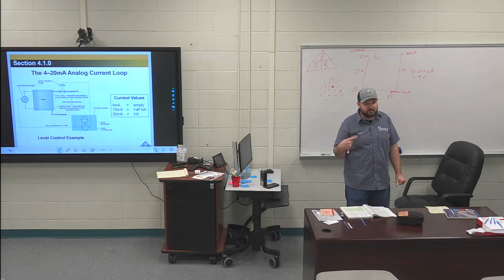A characteristic of an isolated electrical circuit is that the current will be constant at every point along the circuit. Therefore, current makes a better carrier for precision signals. So we're saying this stuff is wired in series, right? If I have stuff wired in series, I have a voltage drop across each load. That's why they don't use 1 to 5 volt signals. But my current is the same at every series load. So that's why it's easier to use a 4 to 20 milliamp.